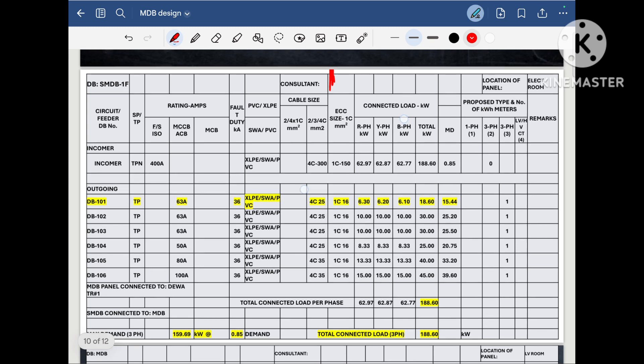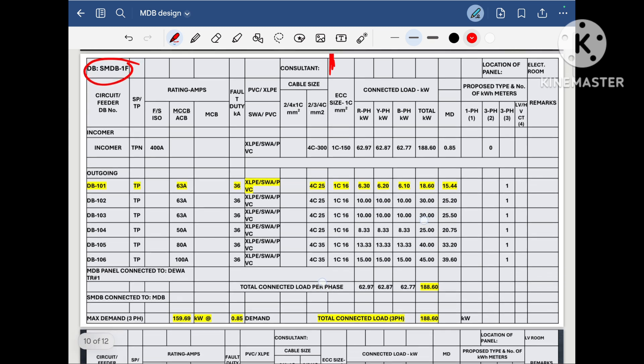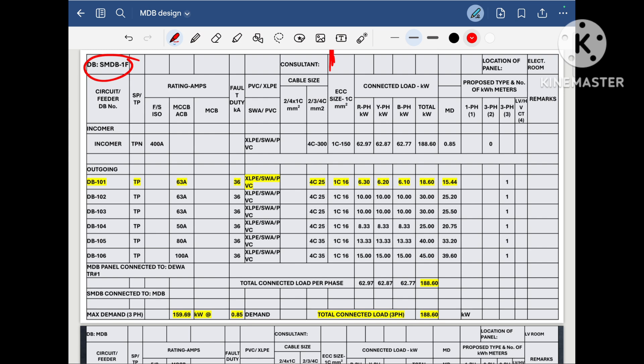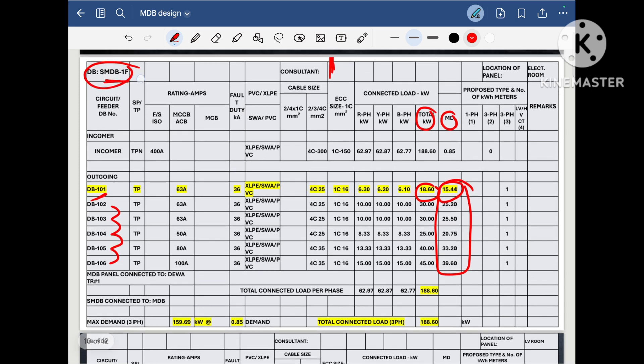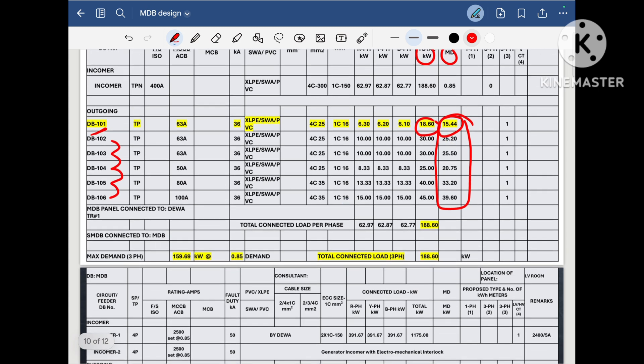Now I have a sub-main distribution board load schedule. This is the DB I just discussed — the total connected load of that DB is 18.6 KW, the demand load is 15.45 KW, which is almost the same. So here I tabulated: 18.6 is the total connected load and 15.44 is the maximum demand. In the same way, for other DBs we will find the total connected load and the maximum demand and sum them up to get the maximum demand load on SMDB first floor.